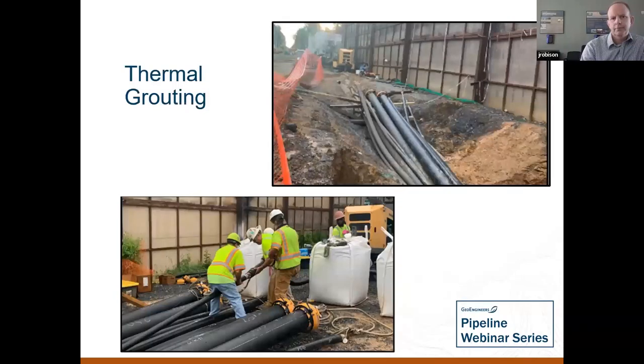So for the thermal grouting, once you have about 50 pounds or so of pressure on the interducts, you just start pumping through the tremie tubes. The tremie tubes have openings at different elevations inside the package, but the idea is to start the grout from the bottom up, and you pump until grout comes out the tubes.